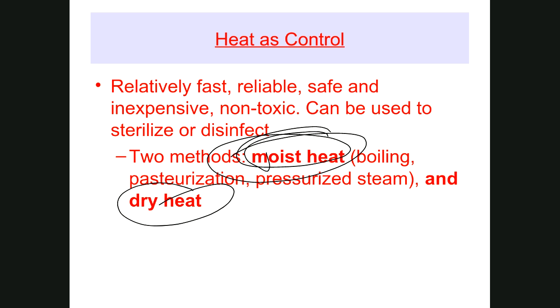Steaming water, 220 degrees. Would you stick your hand inside an oven at 220 degrees, not touching the heating elements, and would you get burned? No, you wouldn't. You do that all the time. You stick your hand in a 350 degree oven to get something out, and you don't get burned. Did I say centigrade? I meant Fahrenheit. 350 degrees Fahrenheit is way past boiling water, and you stick your hand in that oven without worry, as long as you don't touch any surface, because the air itself is not hot enough to burn you, whereas the steam from 220 degree Fahrenheit boiling water is hot enough to burn you. That's the difference. The steam penetrates, so it's definitely more effective.